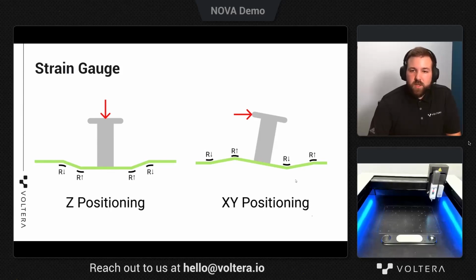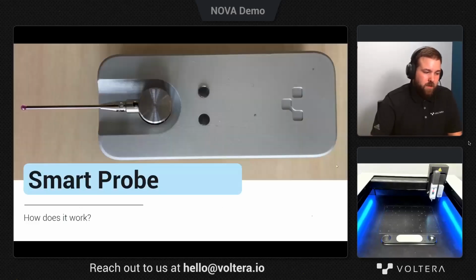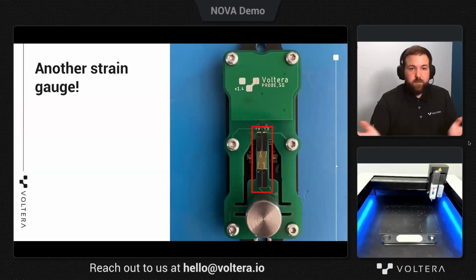Similarly with the XY positioning, the tool will make contact with 4 sides of the tool, much like it does with the V1. Just instead of hitting from the inside, it's hitting from the outside. So we're still getting kind of a compass north, south, east, west type of points. But in this case, the resistors act a little bit differently. So the outer resistance, when the edge is touched, the resistance will go down, as we can see, it's being compressed. And then the one closest to it here is going up. But instead of the Z positioning where the opposite side mirrors it, the opposite side is flipped. So we can see the resistance go down on the closest one and the resistance go up on the furthest one. And so that's how we know which side is being touched based on those resistive values. So the smart probe, how does it work? It's very simple. Another strain gauge sensor.